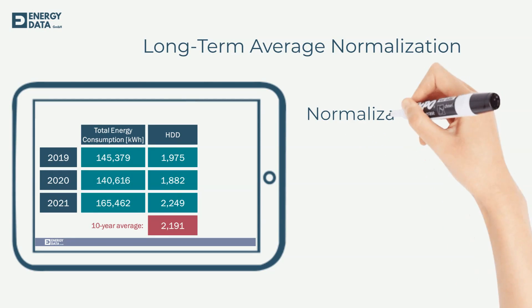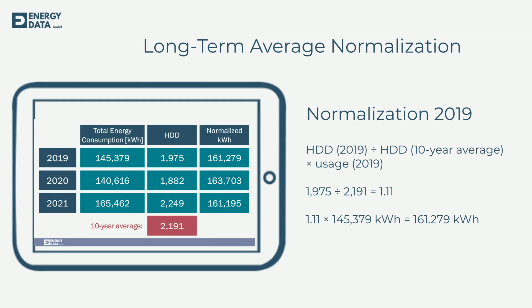To normalize the energy consumption, you check how many degree days in your period there have been compared to the long-term average. This factor will be multiplied by the actual usage, and the result is normalized usage in kilowatt hours. As we already noticed, 2020 had weather-corrected the worst energy performance.